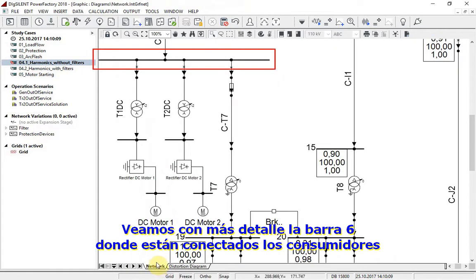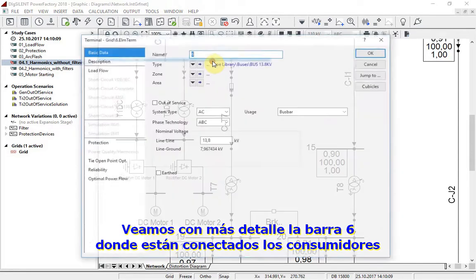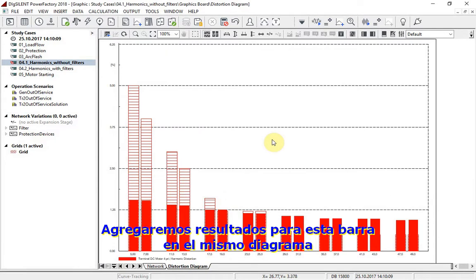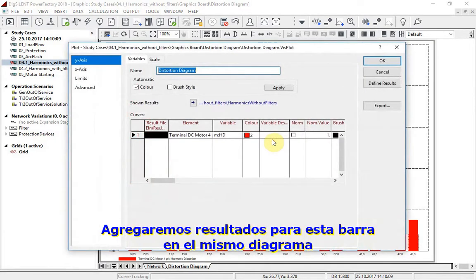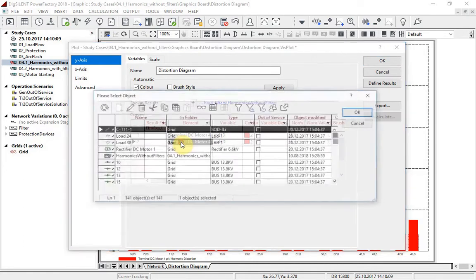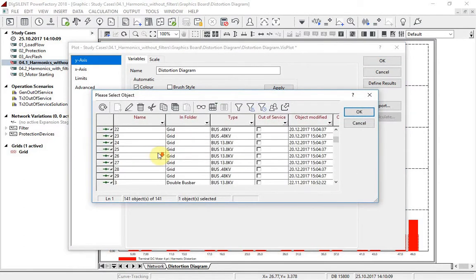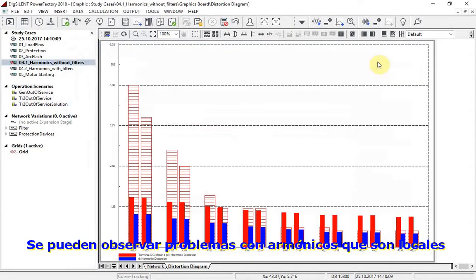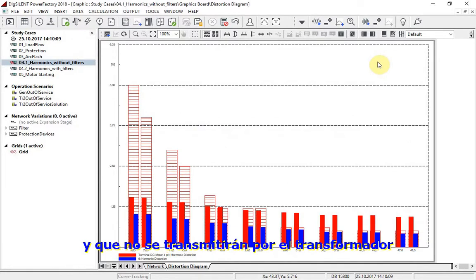Let us have a look at bus bar 6, where this consumer is connected. We will add results of this bus bar on the same diagram. As we can see, the problem with harmonics is just a local issue and will not be transmitted over the transformer.